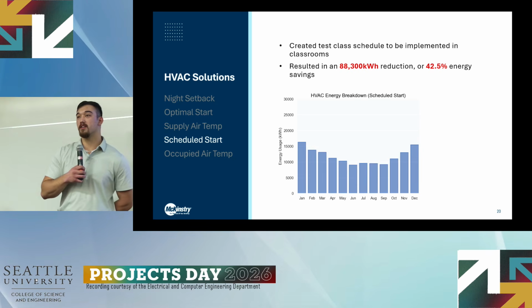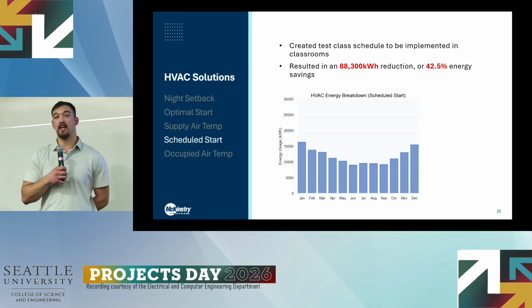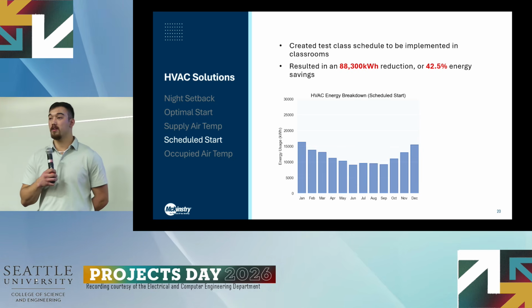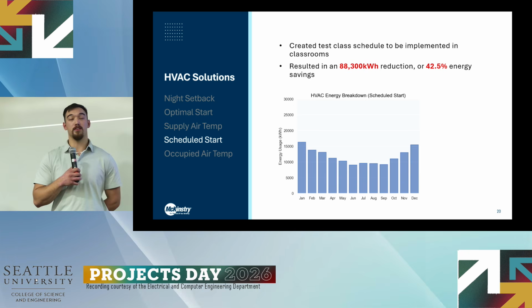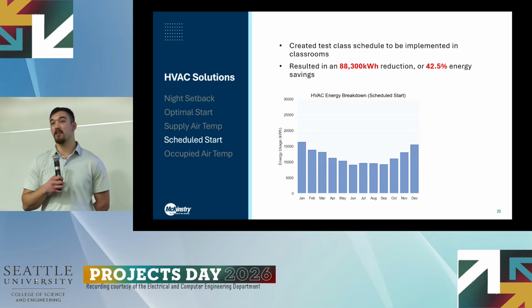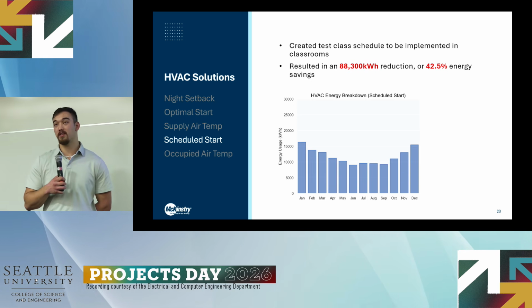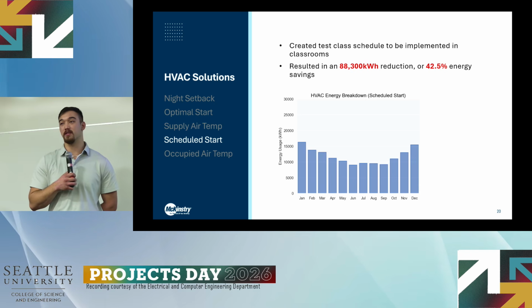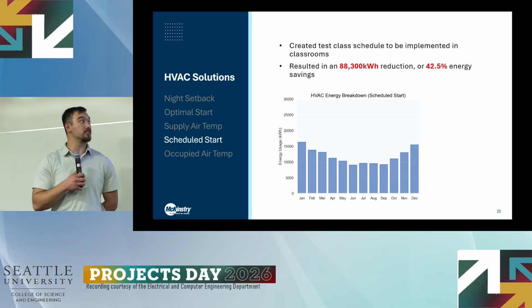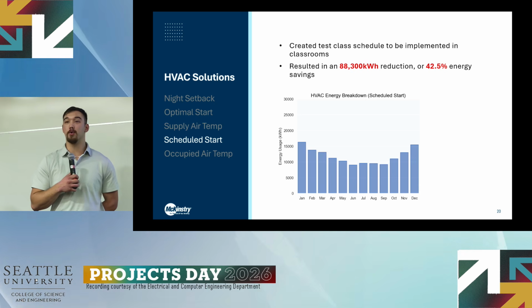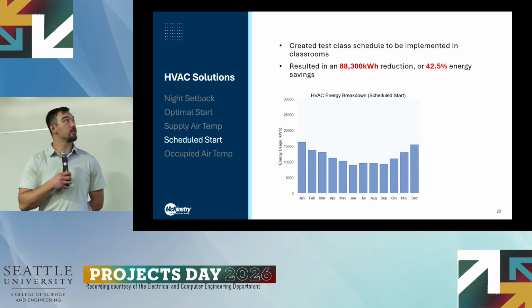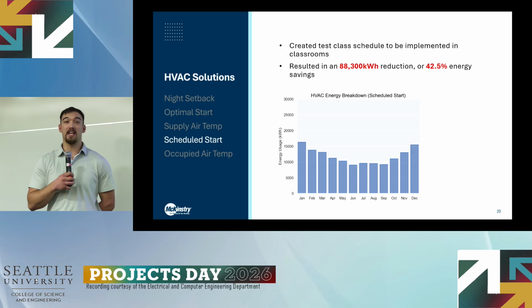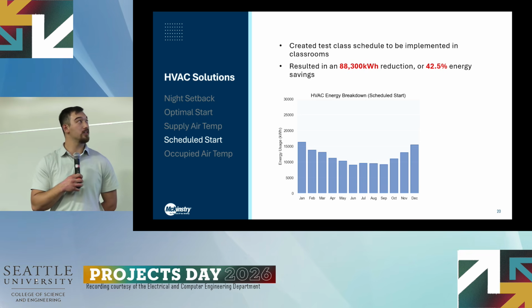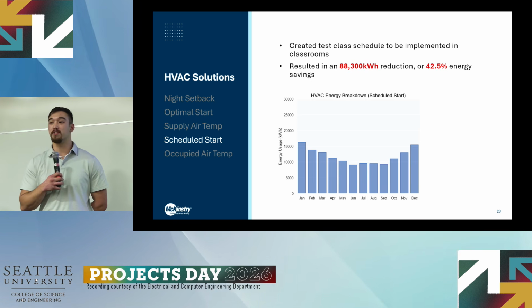For scheduled start, this allowed us to classify the building as unoccupied for a lot longer, meaning we no longer have to take in outside air to condition. And since we don't have to condition that outside air, that saves energy. This is per ASHRAE 62.1. And with that, that resulted in a whopping 88,000 kilowatt hour reduction, or 42.5% energy savings.